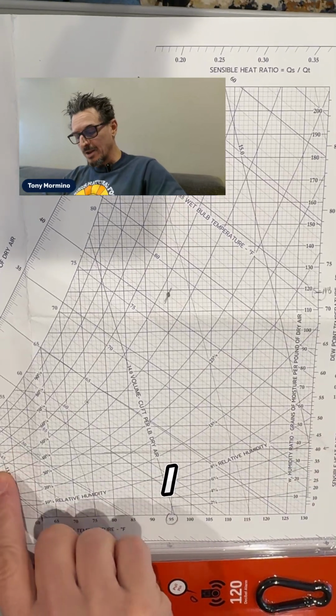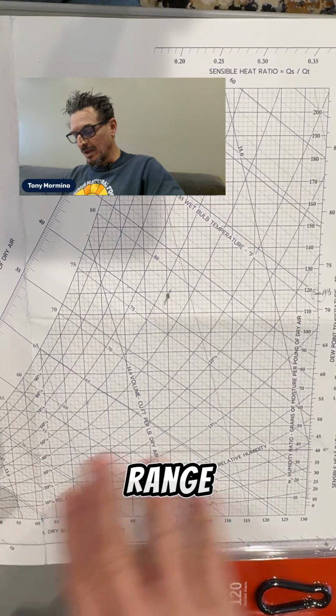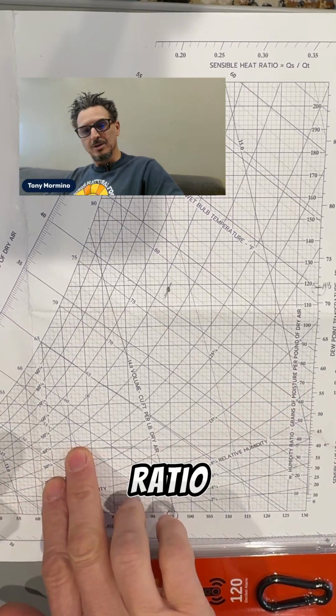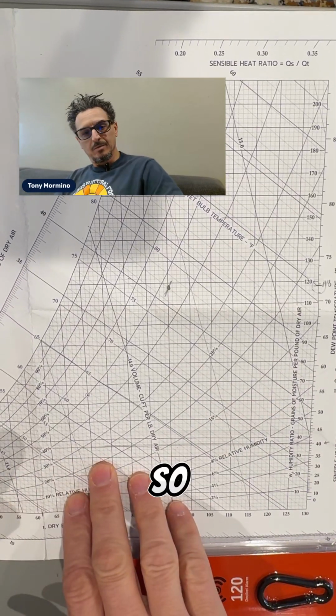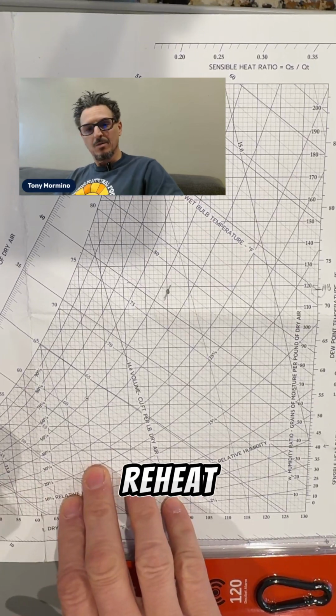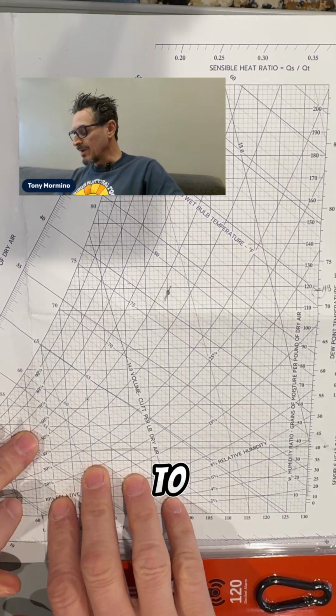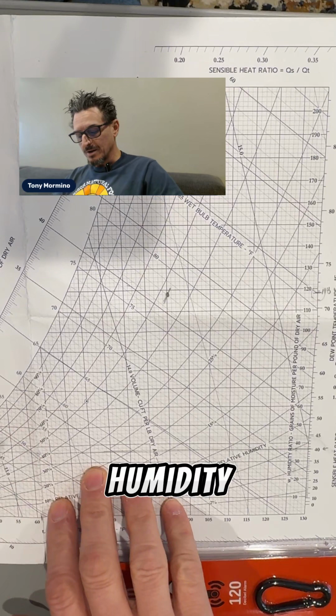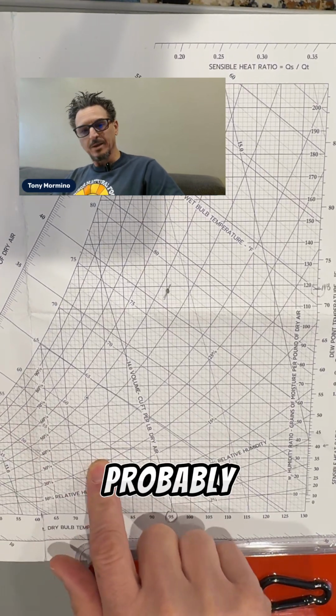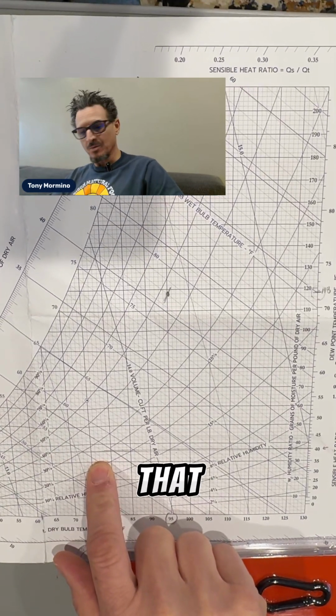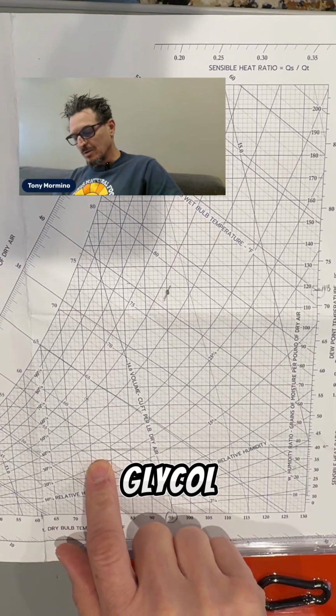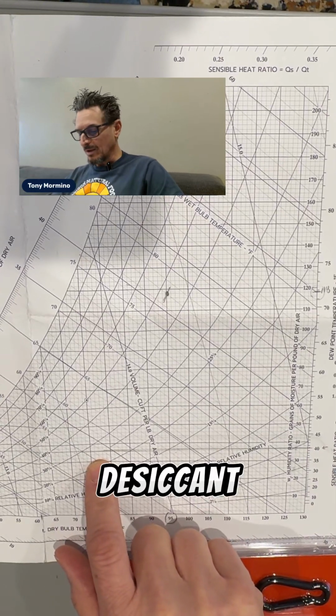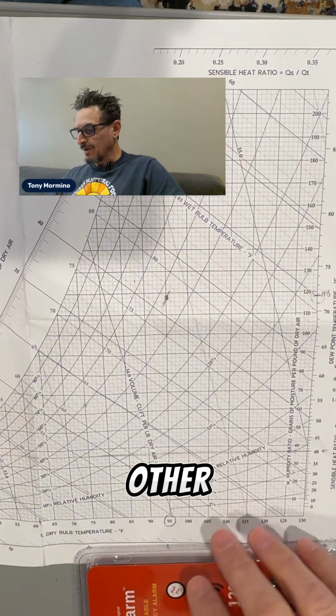Big shocker, right? So I know that I need to be somewhere in this range, and depending on the sensible heat ratio, I can determine if I need reheat or what other features I need in the equipment to meet the desired space temperature and humidity. So if it's 40 degrees, probably into some sort of a desiccant product at that point, maybe glycol or a combination of DX and desiccant. It would depend on many other factors.